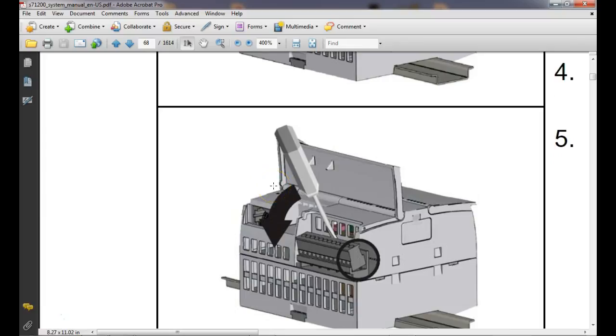It'd be easier to connect if it was off the PLC, but the primary purpose is for us to do real fast maintenance. So what happens if we got a PLC that goes bad? Well, instead of me going up there and having to rewire the whole thing, I can just take the PLC that's out there, pop its terminals out, bring in a new one, put it in there, pop them in, upload the programs. Hopefully you keep backups of your programs, right? Upload the new program and you're ready to go in a matter of basically minutes, right?